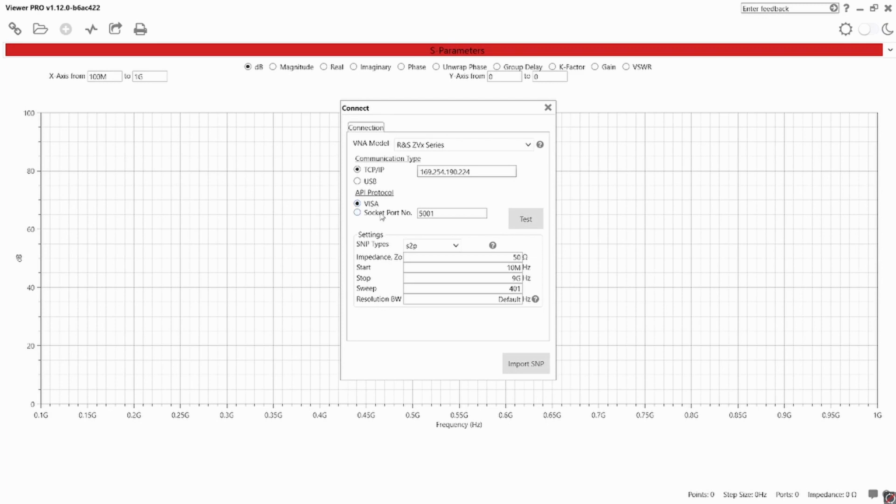Before proceeding to the SNP file setup, this test button is able to test the VNA connection. It will take some time to establish the connection. If it fails, check the previous settings. Make sure they are correct. After the connection is successful, set up the SNP settings.